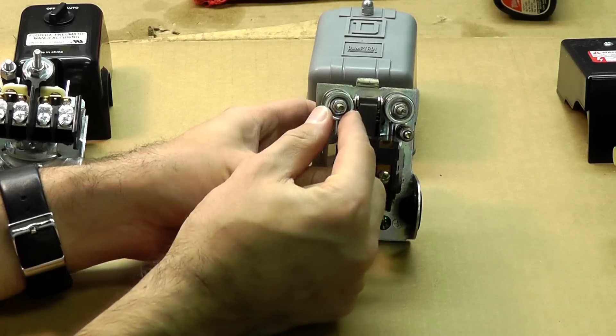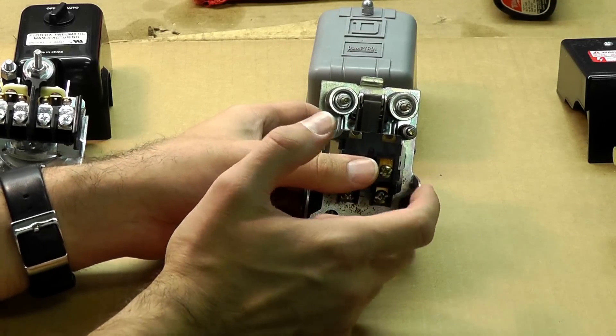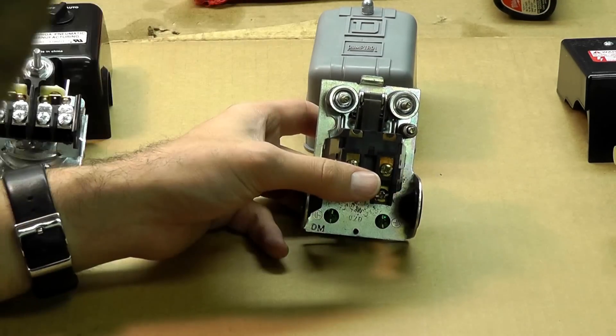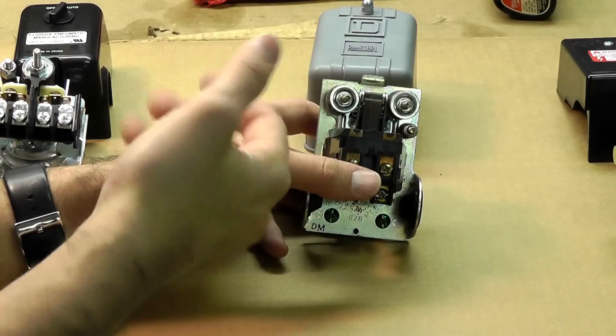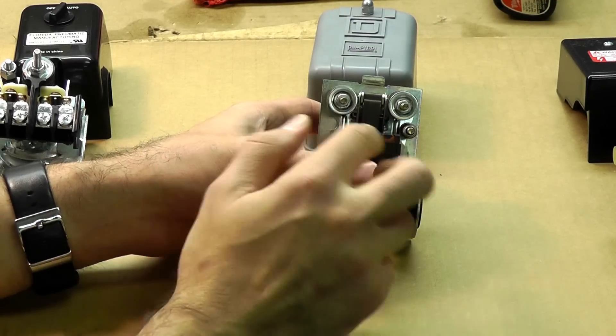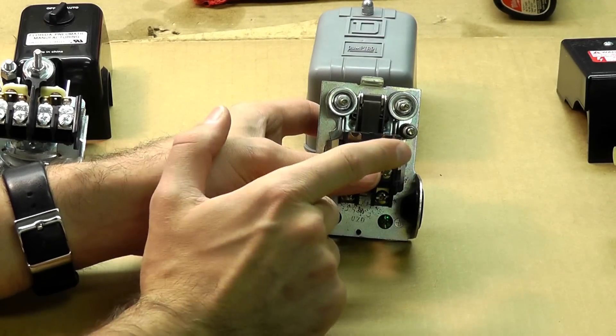So what you do is take this nut—you'll turn it clockwise to increase the cut-in pressure of the compressor. So it cuts in at 95 psi, 120 psi, what have you. This will adjust that. Turn it clockwise to increase the cut-in pressure, counterclockwise to decrease the cut-in pressure. That's what these two adjustments are.